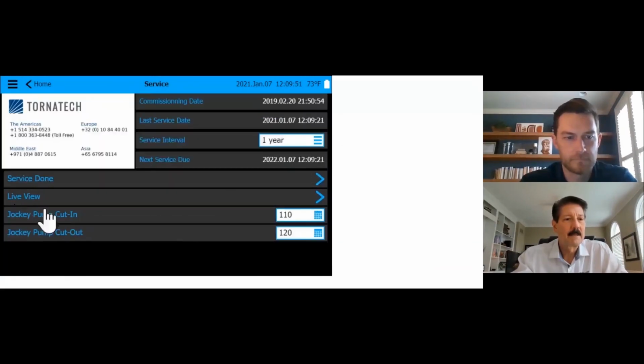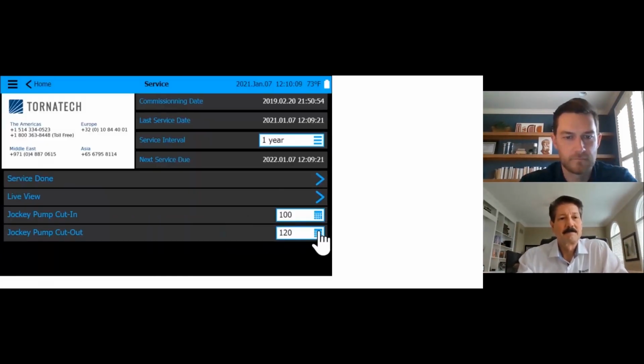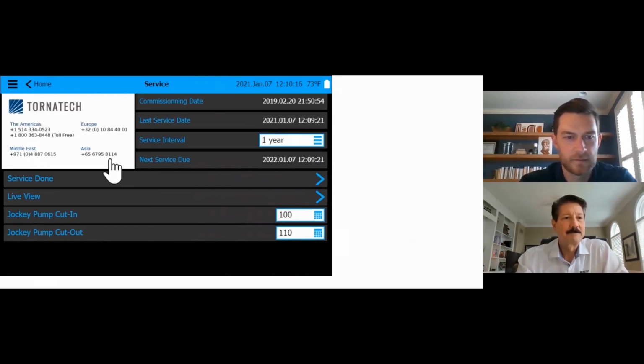One other area. If you don't set the jockey pump cut in, cut out when you're doing commissioning, you can always go to this screen, unlock it, and you can adjust the jockey from here. You can change it to whatever you need to do. It's quite easy.